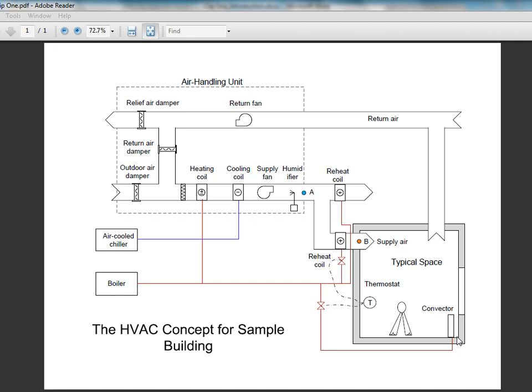Perimeter hot water baseboards shall be located along exterior walls to compensate for heat losses through the building envelope in winter. The reheat coil and baseboard shall be controlled by a space thermostat. Air diffusers, not shown in the schematic, shall distribute the air throughout the spaces from the ceiling level.